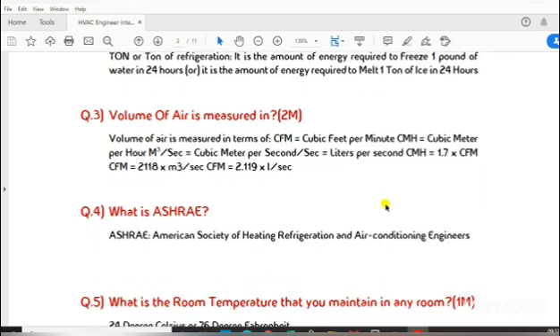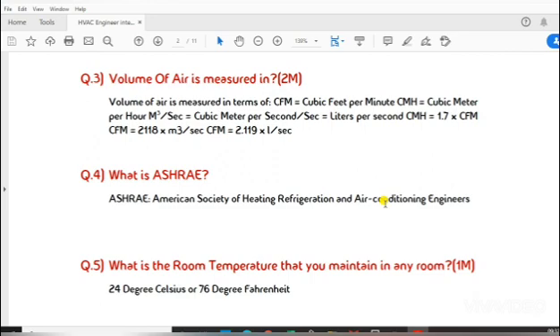Question 3: Volume of air is measured in terms of CFM equals cubic feet per minute, CMH equals cubic meter per hour, M³/sec equals cubic meter per second, L/sec equals liters per second. CMH equals 1.7 times CFM. CFM equals 2118 times M³/sec. CFM equals 2.119 times L/sec.